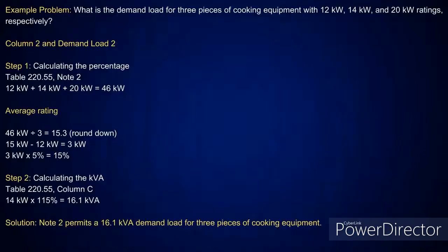Now, the next one, let's look. I've got a 12, 14, and 20. These are not all the same rating. Since they're not of the same rating, I'm going to look at note 2, which is over 8 3/4 through 27 of unequal ratings. What that's telling me is I've got to get an average rating of each one of those. So I'm going to add up the 12, 14, and 20 kW, which gives me 46 kW. Since I have 3 units, I'm going to divide it by 3, which is going to give me 15.3. So I'm just going to round down to 15 kW.